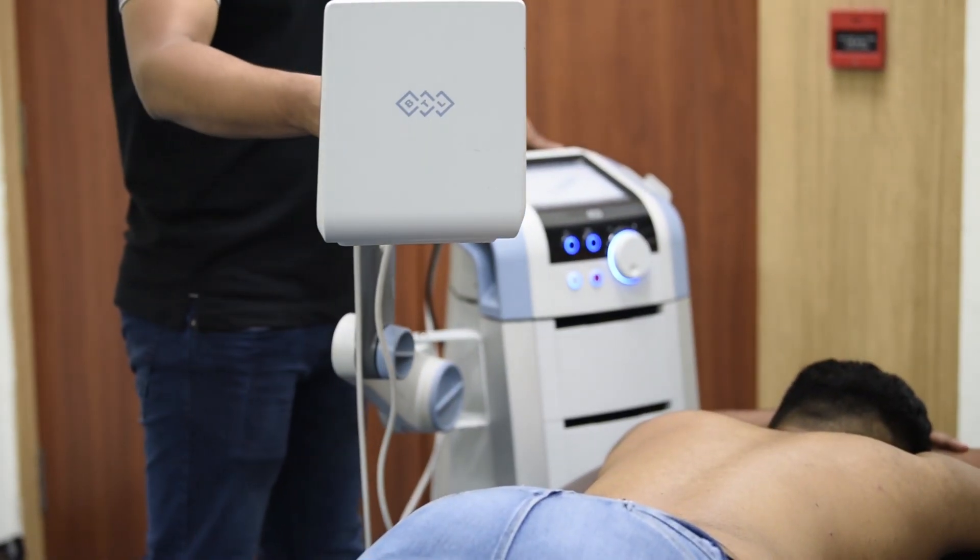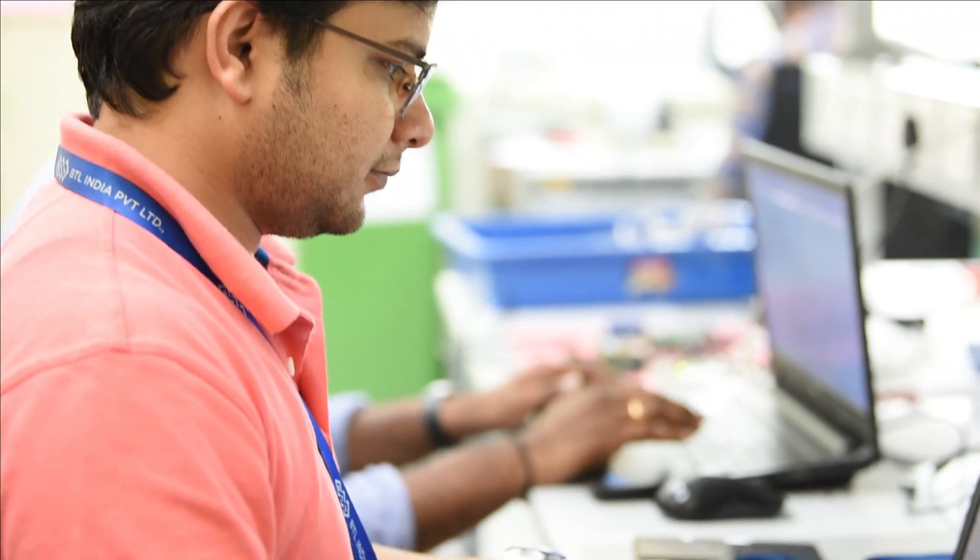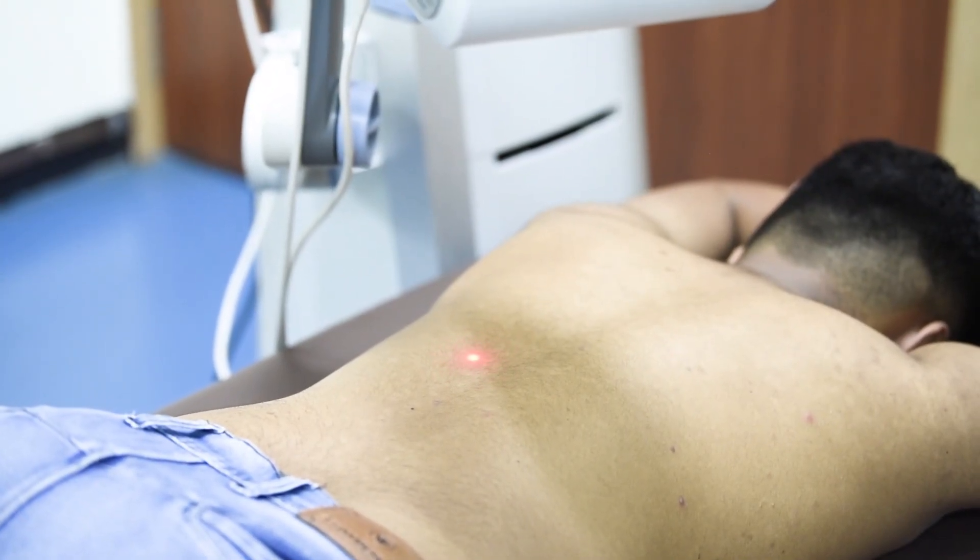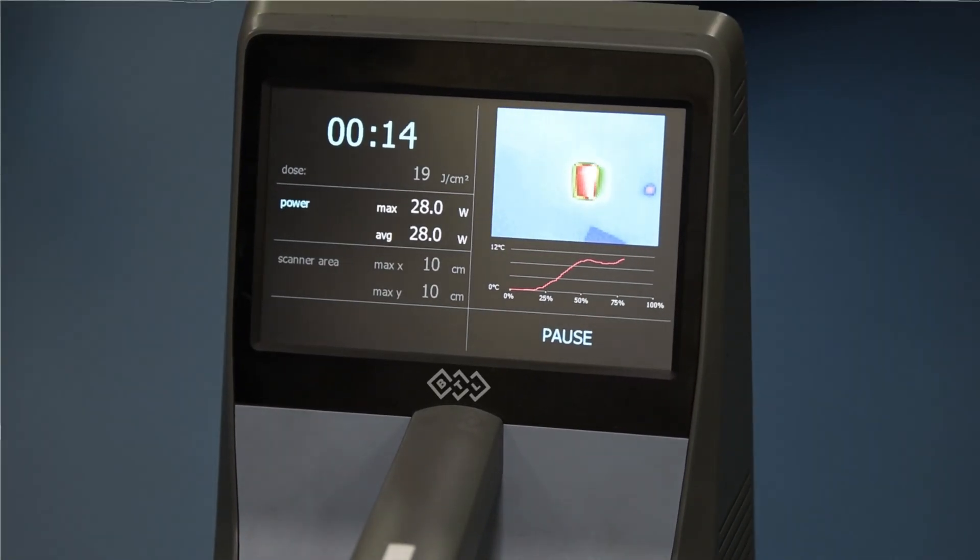We developed multi-process systems which have features like laser drive control, pattern generation, patient safety, and treatment detection. We are running a complex algorithm to generate different therapy patterns and we are able to achieve uniform thermal spread. Various safety protocols are implemented using various sensors.